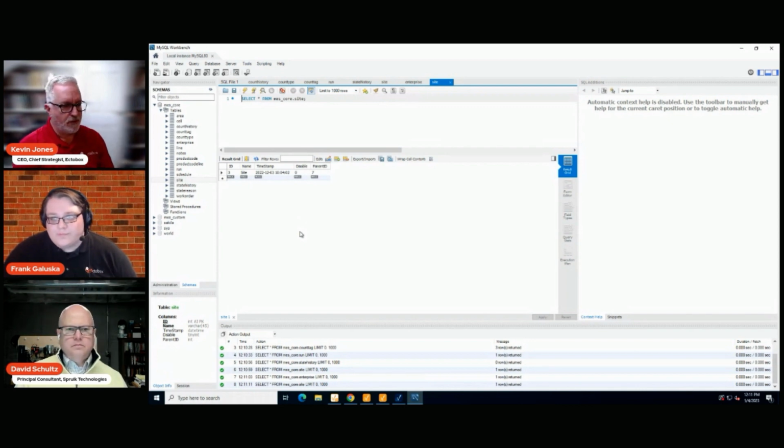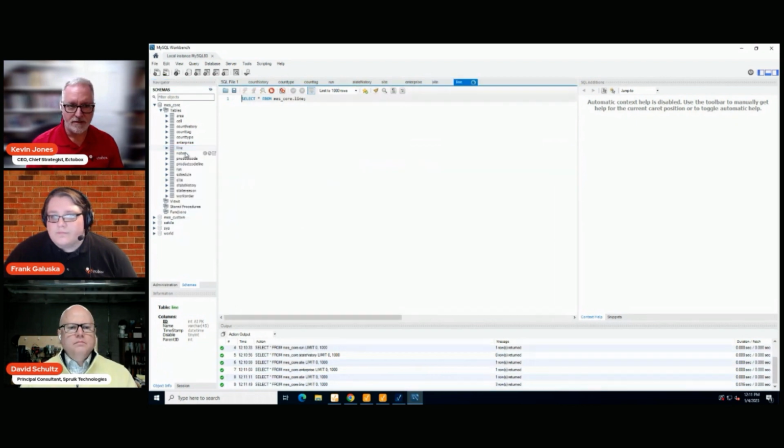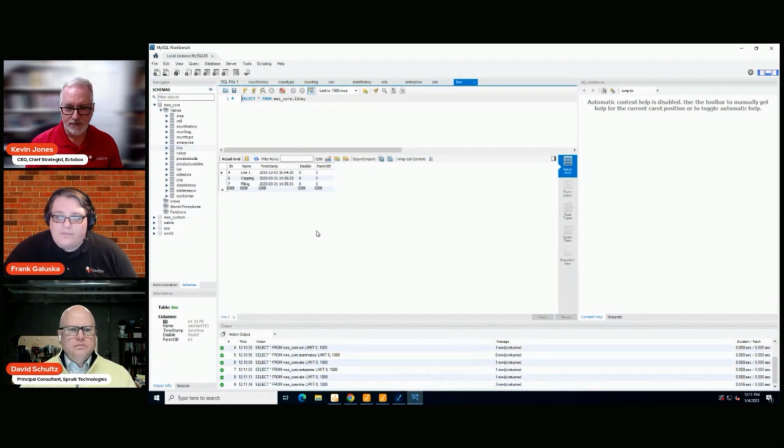So what we're looking at is the count history table that we saw where the data is going, and then you're talking about that ISA architecture of enterprise, site, area, line, cell that we use in the UNS, and that data is stored in separate tables, enterprise table, site table, etc., and they are related to one another with relational databases between a primary key and a foreign key, and that gives you the flexibility to set up all kinds of sites and locations and areas and assets and all the rest of that kind of stuff. Is that a good way to go ahead?